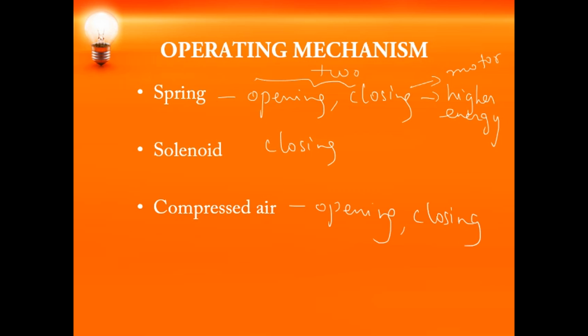Why? Because the closing spring should usually be operated by a motor. That is why springs are very good for opening, because their force is very large. And for closing purposes, solenoids are very good. That is because the force of attraction of the solenoid will increase when the distance between the contacts reduces. So why are solenoids not used for opening? That is because they are very slow in their action.